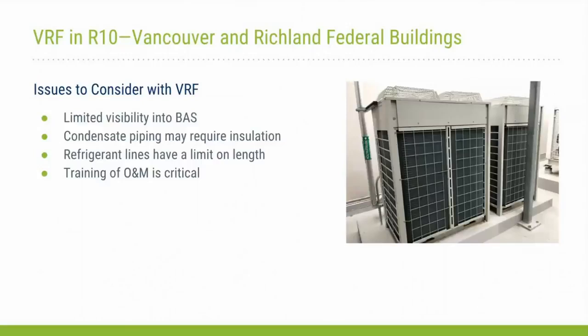So we didn't know whether we had a failure of that booster pump for the condensate, and it overflowed into our courtroom area because we didn't know it was an issue. So there's issues with condensate. You have to insulate it if you're going to have humid conditions. So there's just concerns associated with the condensate that it's done correctly. And if it's gravity and there's no pump at the unit, we've got to make sure we individually trap those units so that they can drain properly.